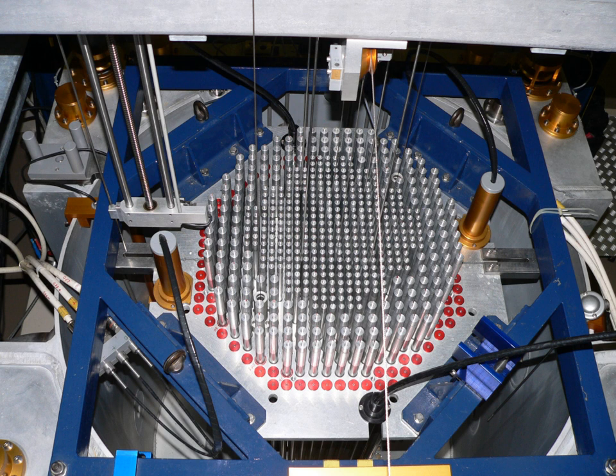If the coolant is a moderator, then temperature changes can affect the density of the coolant moderator and therefore change power output. A higher temperature coolant would be less dense, and therefore a less effective moderator.